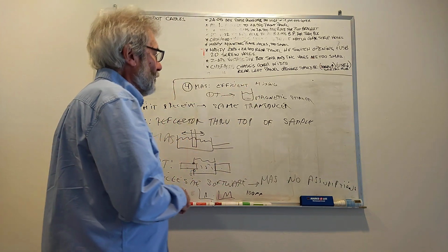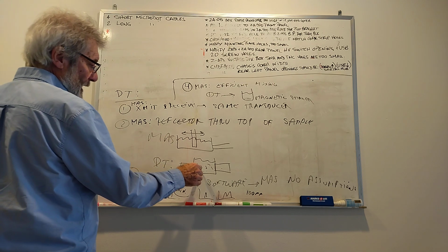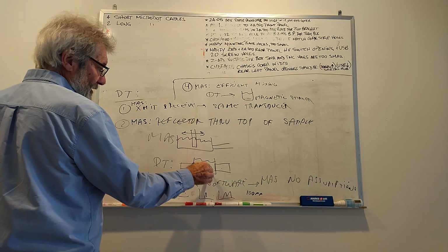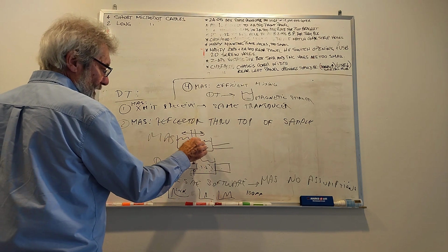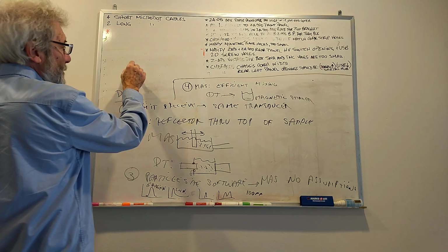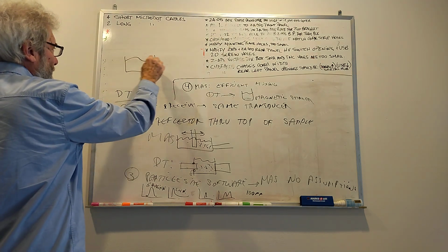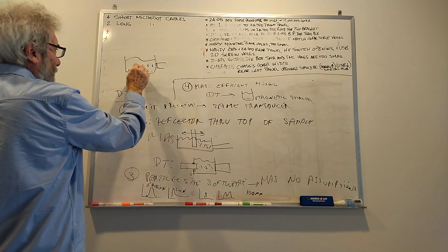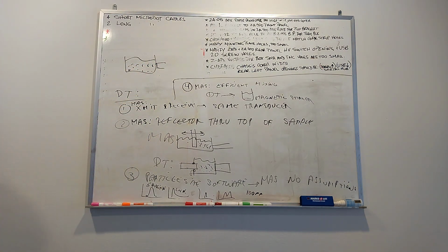another advantage for sample mixing because when you make a sample measurement, you need to have the particles suspended so that the sound can travel through the particles. But if the sample cell doesn't have enough mixing and you have the particles here and the sound is going here, then the sound does not see the particles.